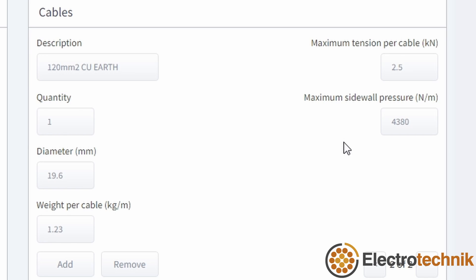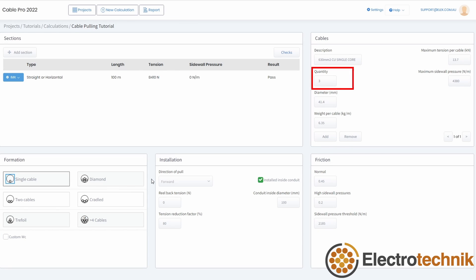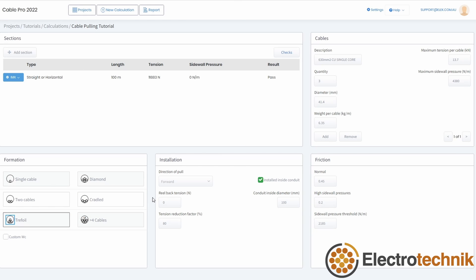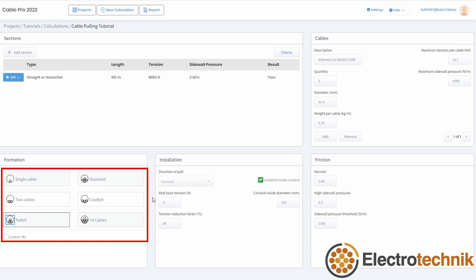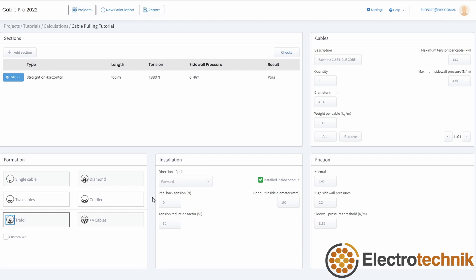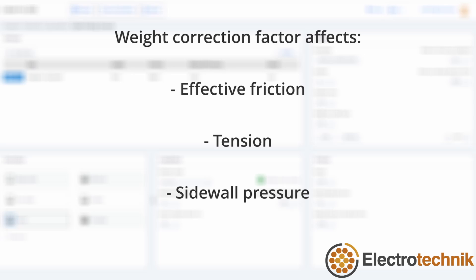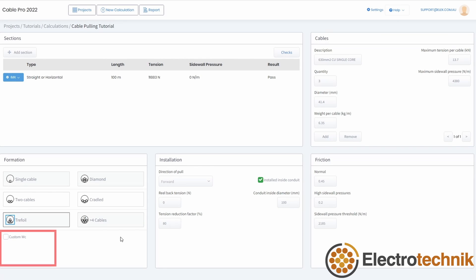Next, let's take a look at the formation section. The number of cables and their formation in the pull affects the overall tension. Make sure to select a formation that matches the total number of cables for all cable types in your pull. For example, if the total quantity equals 4, select the diamond formation; or if the total quantity is 3, select the trefoil or cradled formation, and so on. Depending on the formation selected, a weight correction factor is automatically calculated. Weight correction factor is generally between 1 for a single cable, up to 1.4 for more than 4 cables. It affects friction, tension, and sidewall pressure calculations. Users can also enter a custom weight correction factor — a higher weight correction factor means a higher tension.